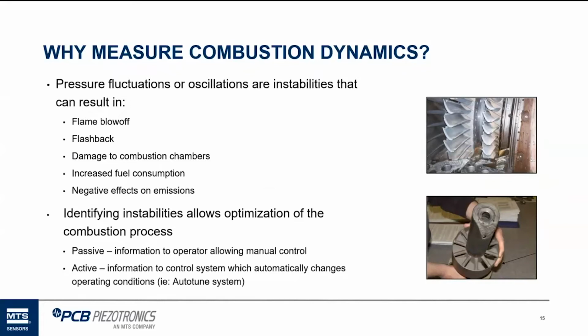And then there's an active system, which is actually tied into the control system and can sometimes provide shutdown if certain extreme limits are reached. A kind of newer product that's been out for probably 7 or 8 years, maybe even 10 now, is an auto tune system. It's tied to the combustion dynamic system all the time, and it can automatically tune the gas turbine while it's running. So it's always going to meet the emissions and fuel air mix ratios that are set up in it. That's a real neat system. It's really expensive, but there are some statistics out there that show that it pays for itself in a very short time.